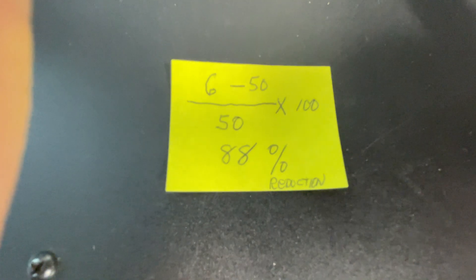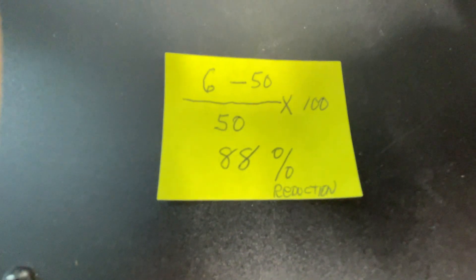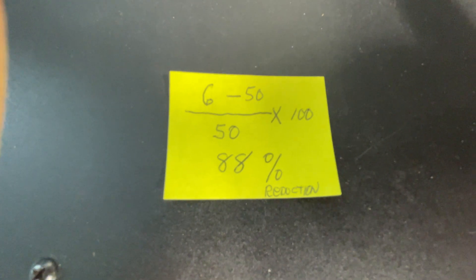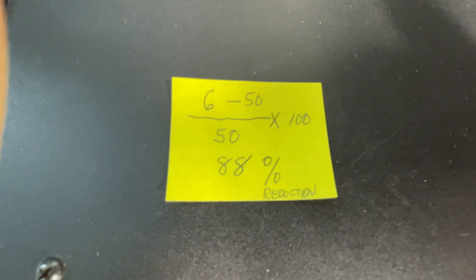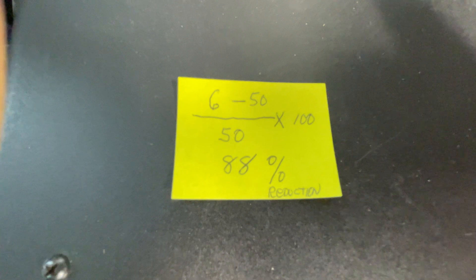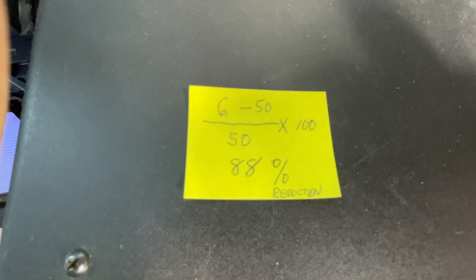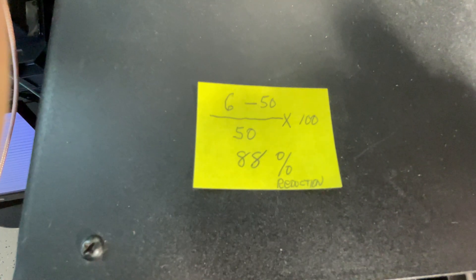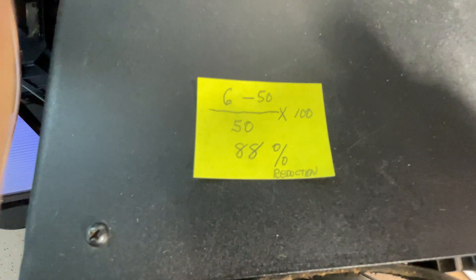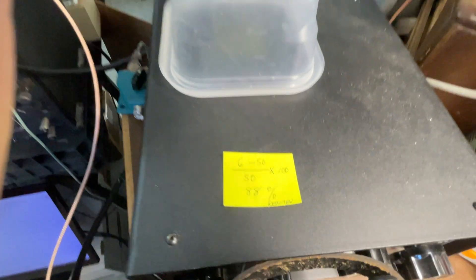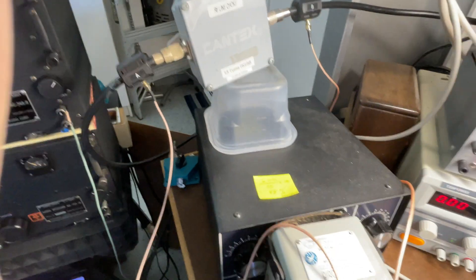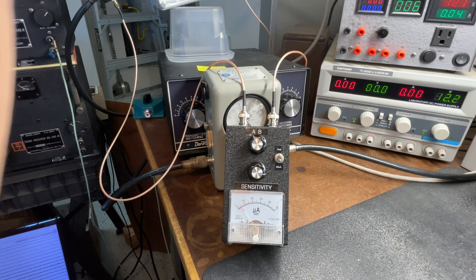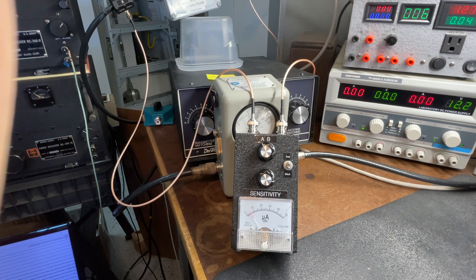An 88% reduction in the common mode current. So we just took 50 coming in minus the 6 coming out of the choke, divided by the incoming 50 microamps times 100. Come up with 88%. I think in the other video it was more towards 97%, which was not accurate. I just wanted to clear the air on that.